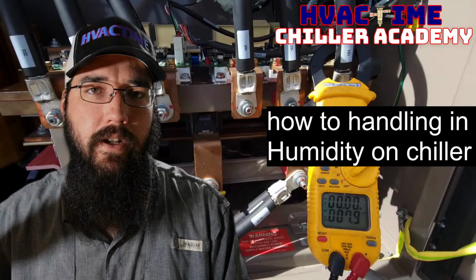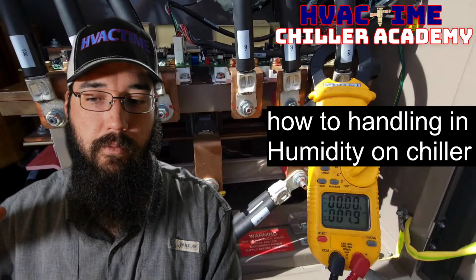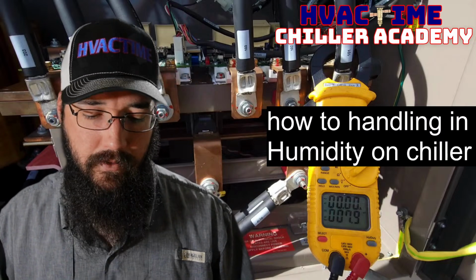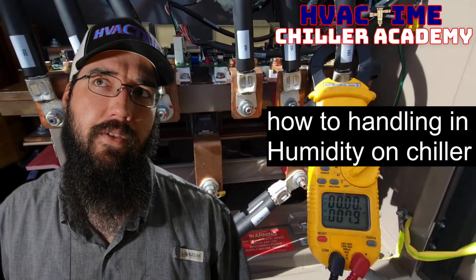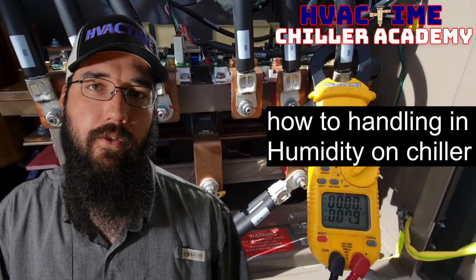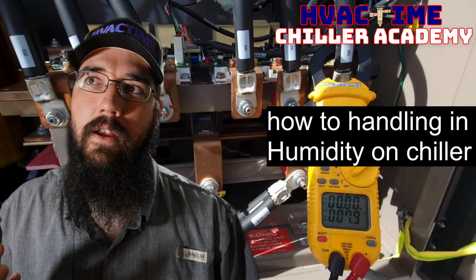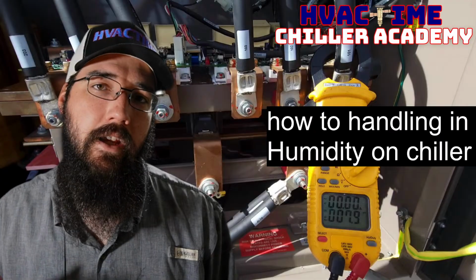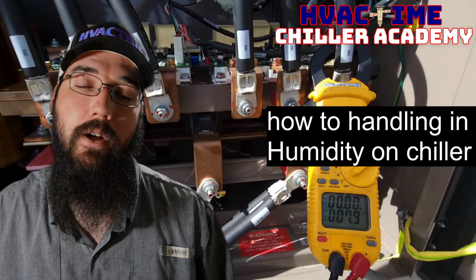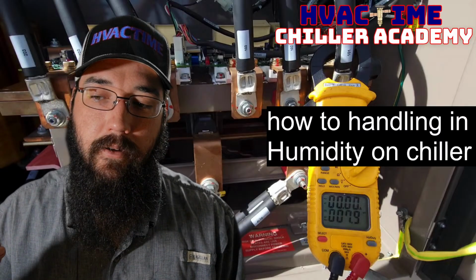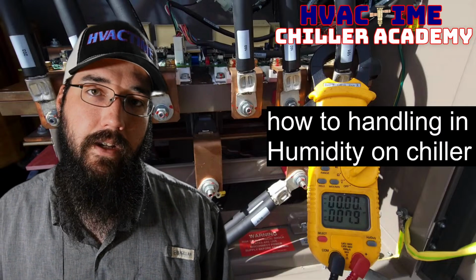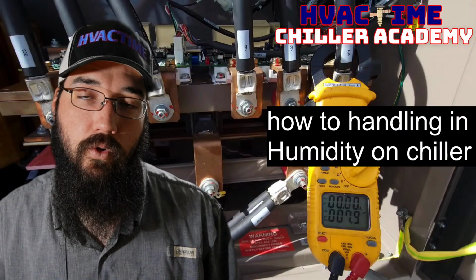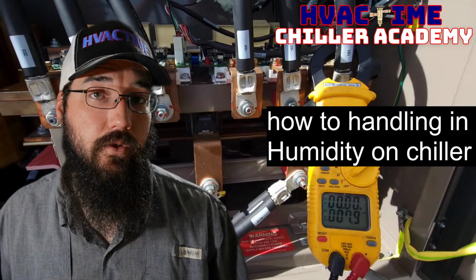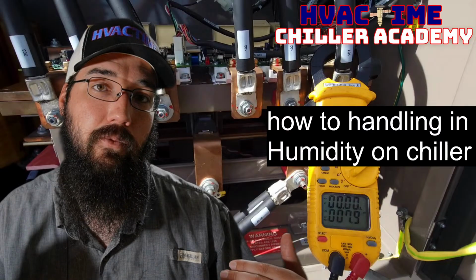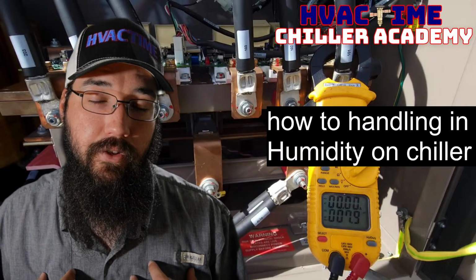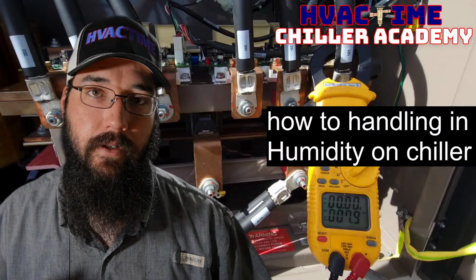Because yes, water, if we've got a coil designed for a 10-degree split across it in terms of 45 in, 55 out, right? If that's our base design, then there's only so many BTUs to be taken in per gallon of water that goes through there. But by lowering the temperature of the water, we're able to take in more of the heat, more of the latent heat. I'm sorry, the humidity. We're able to take in more of the humidity into the coil. So by taking in more of that humidity and having a more latent heavy ratio, by having a colder coil, we can better dehumidify. And this is also true vice versa. If you're struggling with running a really low humidity and you need to keep more humidity in your space, then raising that coil temperature, that will help.